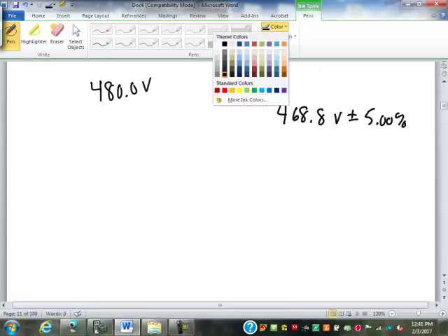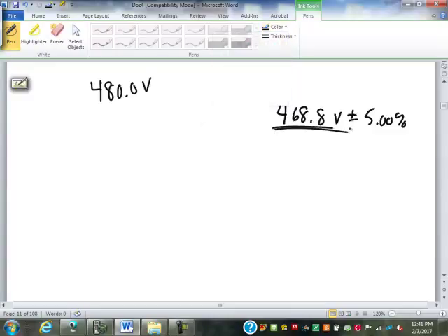So what they're doing, they want you to calculate the actual range across the motor. The measured voltage, what you're getting off your meter, is this amount. And they're telling you to allow 4% off the specified voltage, that's off the 480, for a loss in your wire and loss in the system. So let's figure that out. What is 4% of the 480?